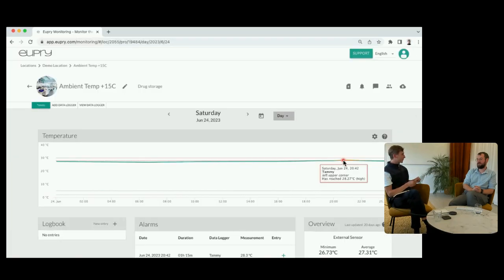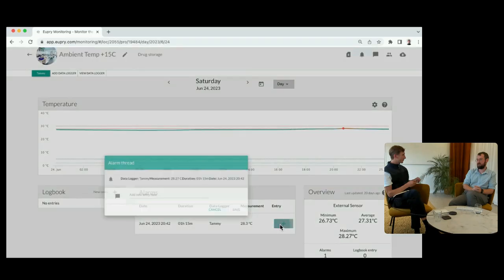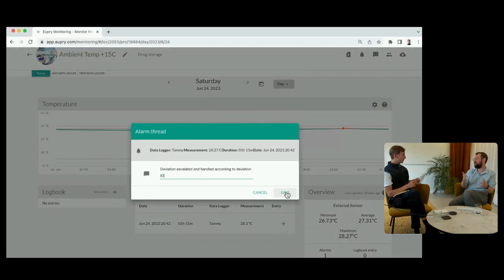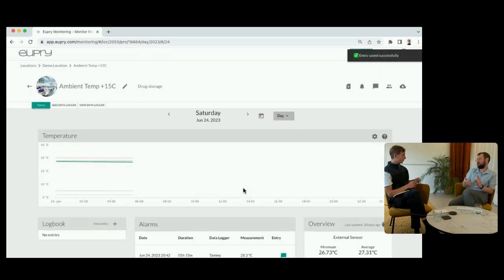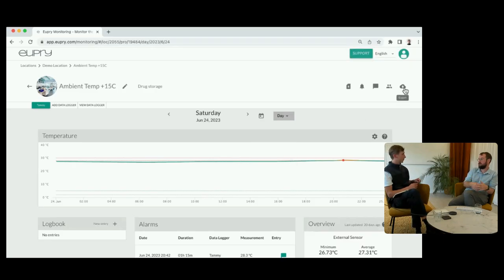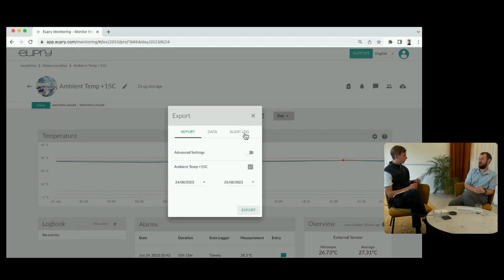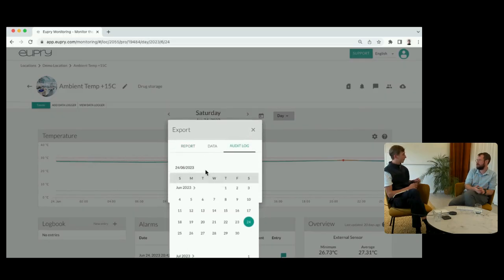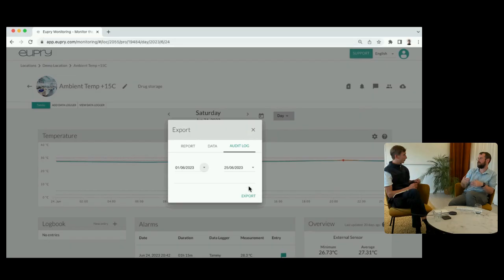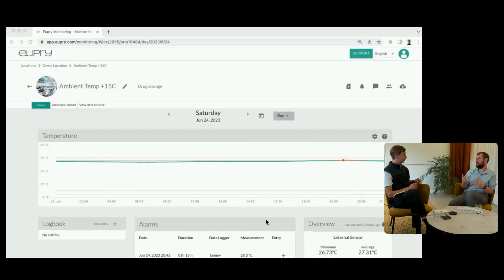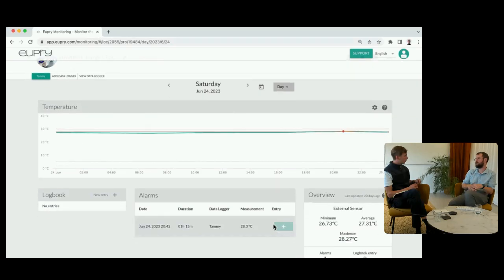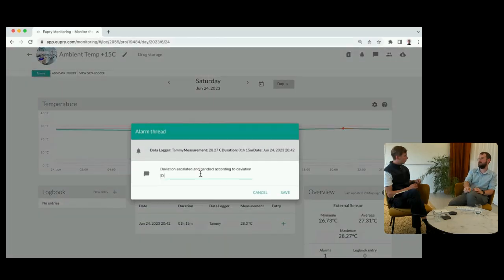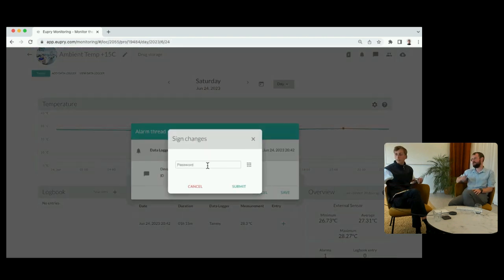And that, in all seriousness, is something we surely hope everyone would adhere to in paper format as well. But in a 21 CFR Part 11 compliant system, you are forced to adhere to the core principles. Records are only recorded at the time of entry. Your signature is always assigned to the action. You can never delete any previous entries. One of the requirements is that any alteration to a record should never obscure the previous record, and all records should be in human readable format and so forth. So that enforces ALCOA, and now it's the ALCOA Plus principles, of course.